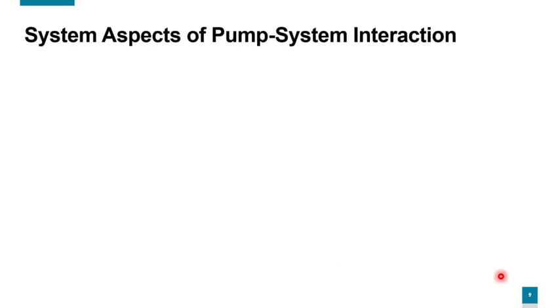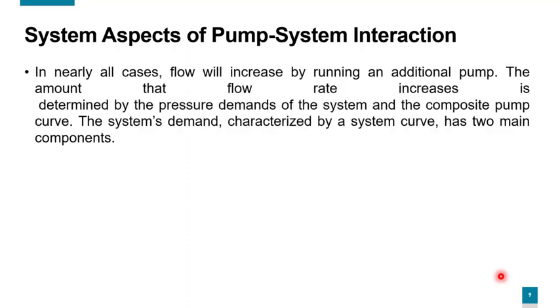System aspects of pump system interaction. In nearly all cases, flow will increase by running an additional pump. The amount that flow rate increases is determined by the pressure demands of the system and the composite pump curve.